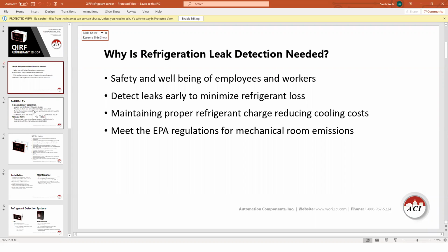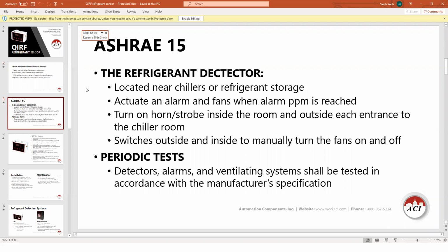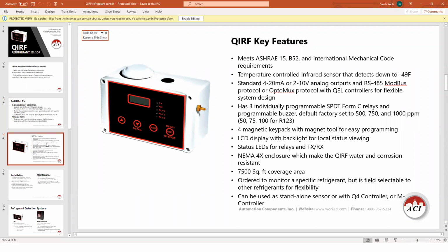To go into the program and change from one refrigerant to another is really, really easy. And that makes it your advantage because you don't need to place an order for another one and wait for it to be shipped. You can just take it off the shelf, change it, and you're good to go and install it. And because these sensors are infrared technology, the sensor lifespan is typically like 13 years. So it lasts a long time. And I know for a fact that it's extremely sensitive. I've got a customer in Indiana who purchased their refrigeration company and they bought like 80 of them. They thought they'd do a test and they were about 50 feet away and they dropped some Freon down and boom, it picked it up just like that. So it's extremely sensitive too.